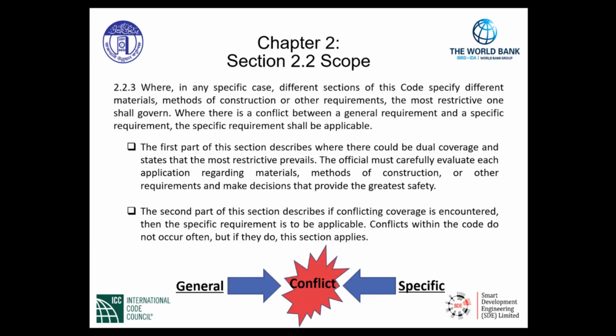In Section 2.2.3, this key section gives us the requirement where, in any specific case, different sections of this code specify different materials, methods of construction, or other requirements. We need to look at the most restrictive one, as that shall govern. Where there is a conflict between a general requirement and a specific requirement, the specific requirement shall be applicable.